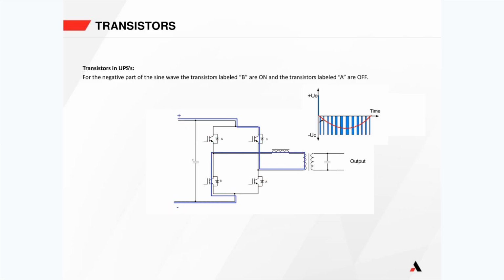Okay, and PWM gives us much tighter regulation on the output of the system because, even though we're switching at 8,000 times a second, we can adjust the width of every single one of these pulses whenever we want. So if somebody puts a huge amount of load on the UPS at one point, we can widen all of these pulses instantaneously to allow for that.